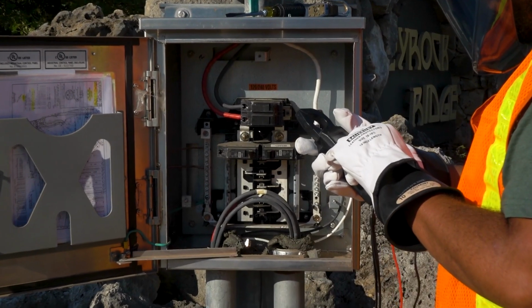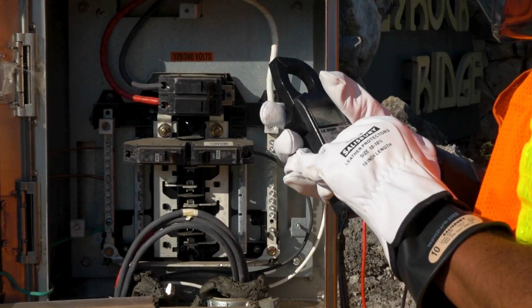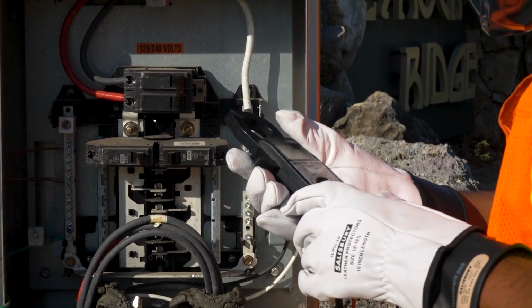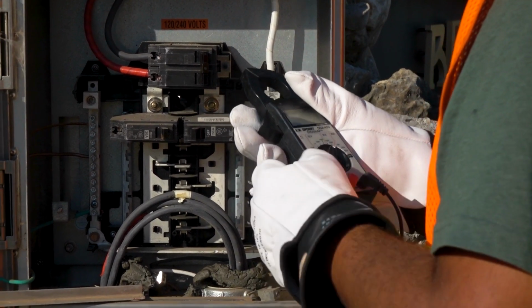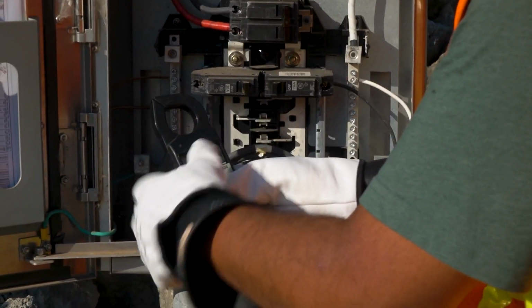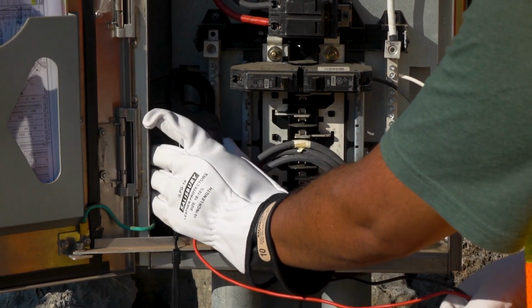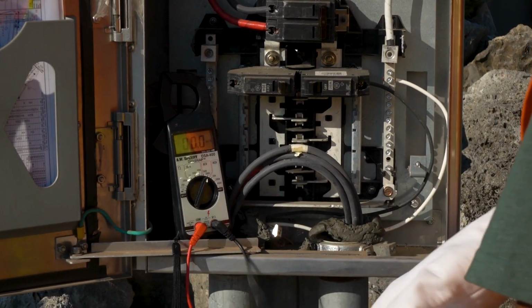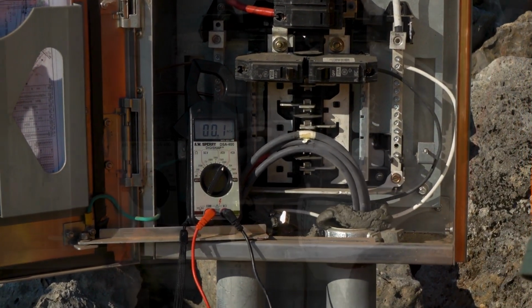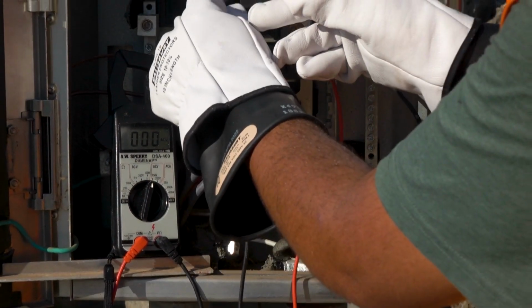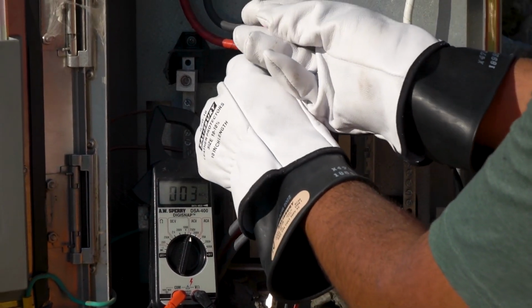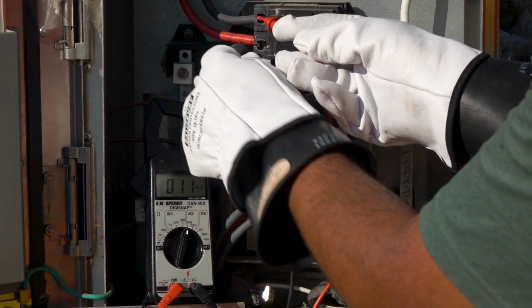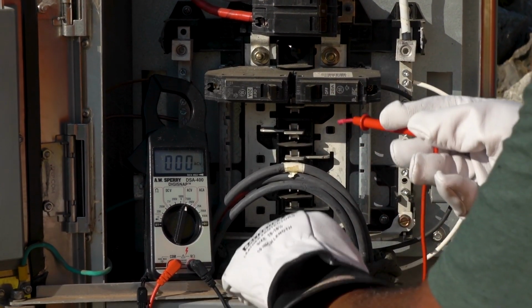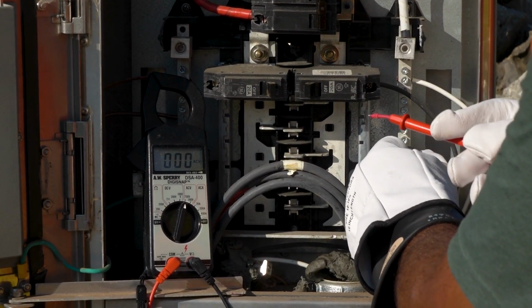Before power is applied to any electrical equipment, and before the contractor places any circuit breaker in the on position, the system's voltage must be verified. This is done by taking readings with a known good voltmeter, provided and operated by the contractor personnel. This important data should be recorded in the presence of either the engineer or the project's electrical inspector.